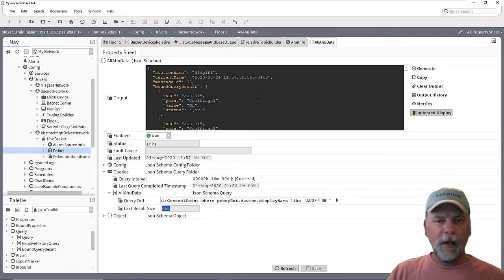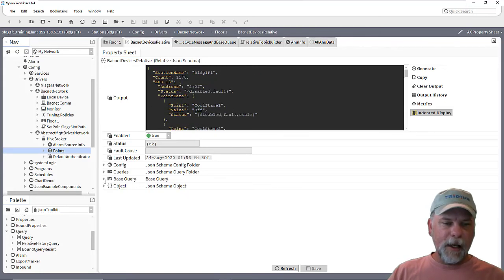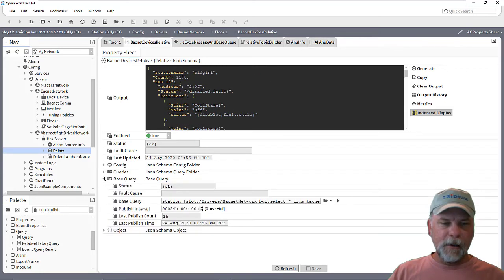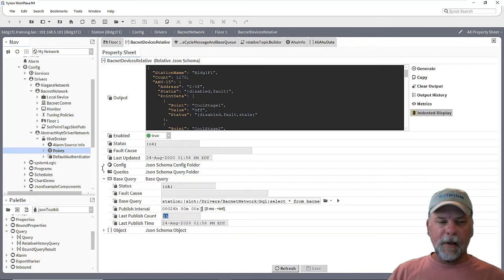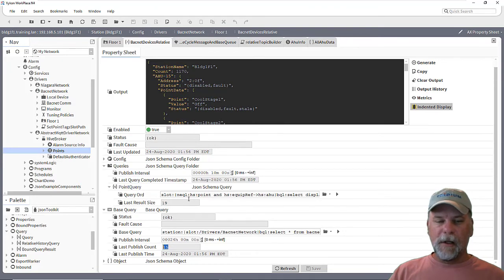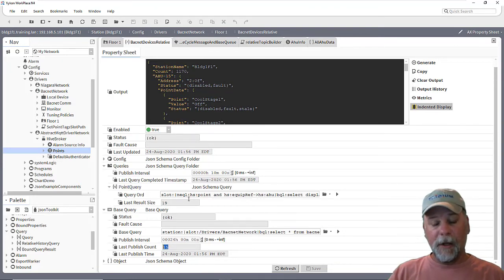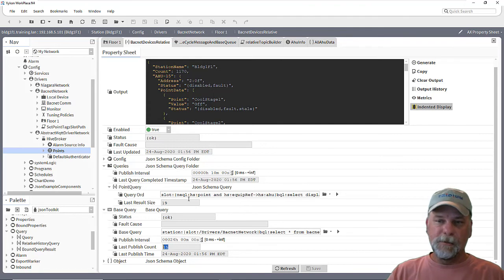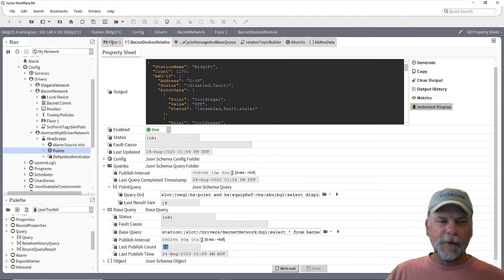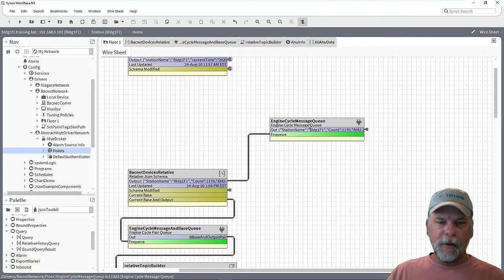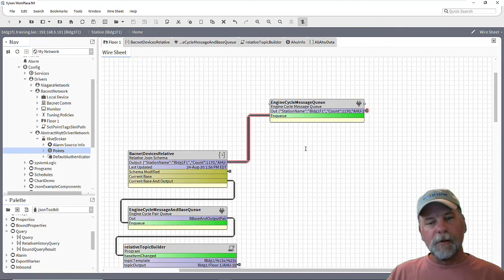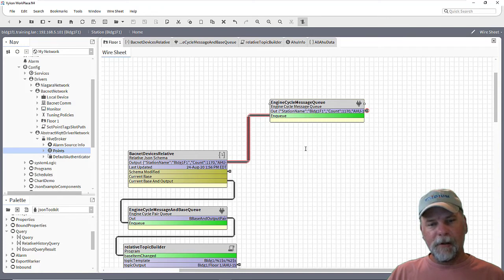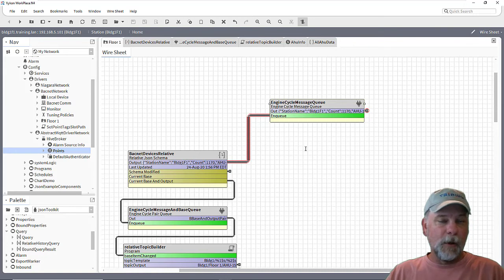But there were other options of using a relative schema where that base query finds, say in this case, 15 devices, and then it will run a subsequent point query against each one of those individuals. So the JSON payload then was specific to just an individual device. And we demonstrated linking through an engine cycle message queue to a single published point where that topic, that single topic was used for all 15 air handlers and it was updated once each, once for each air handler.